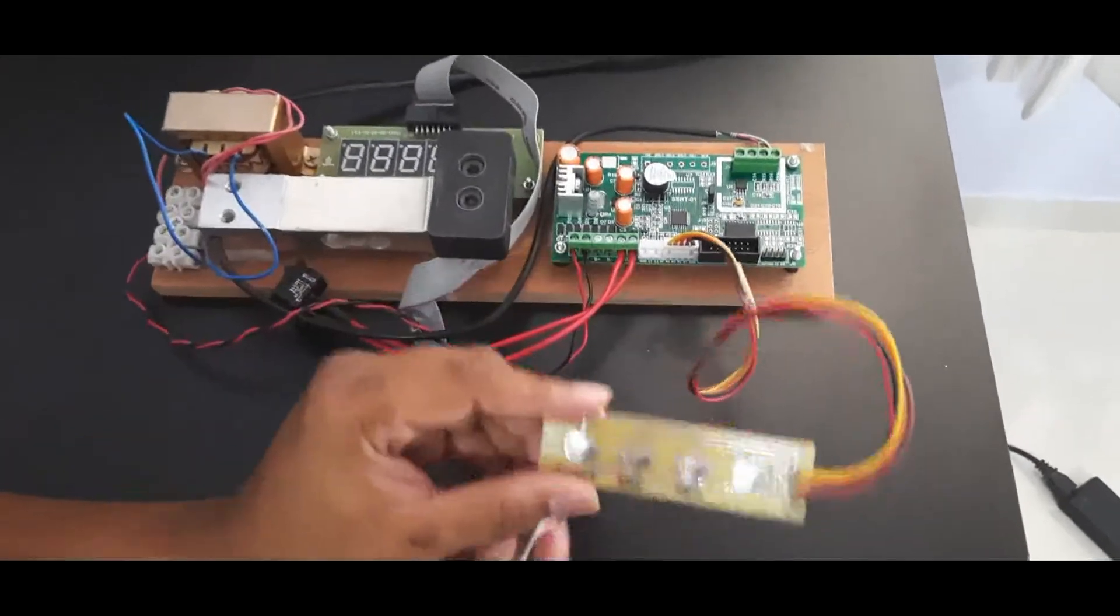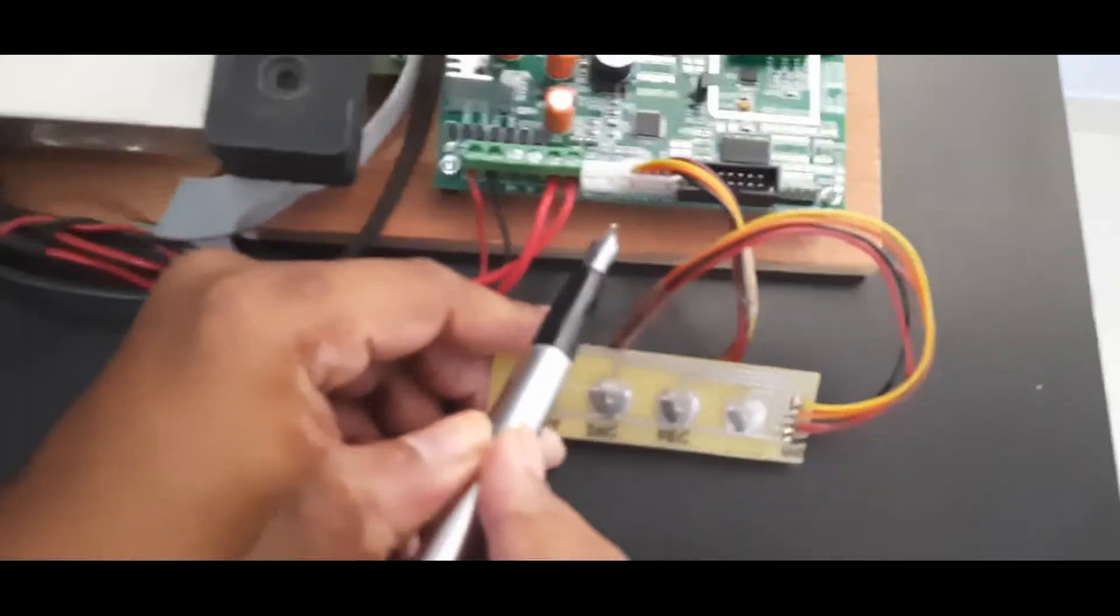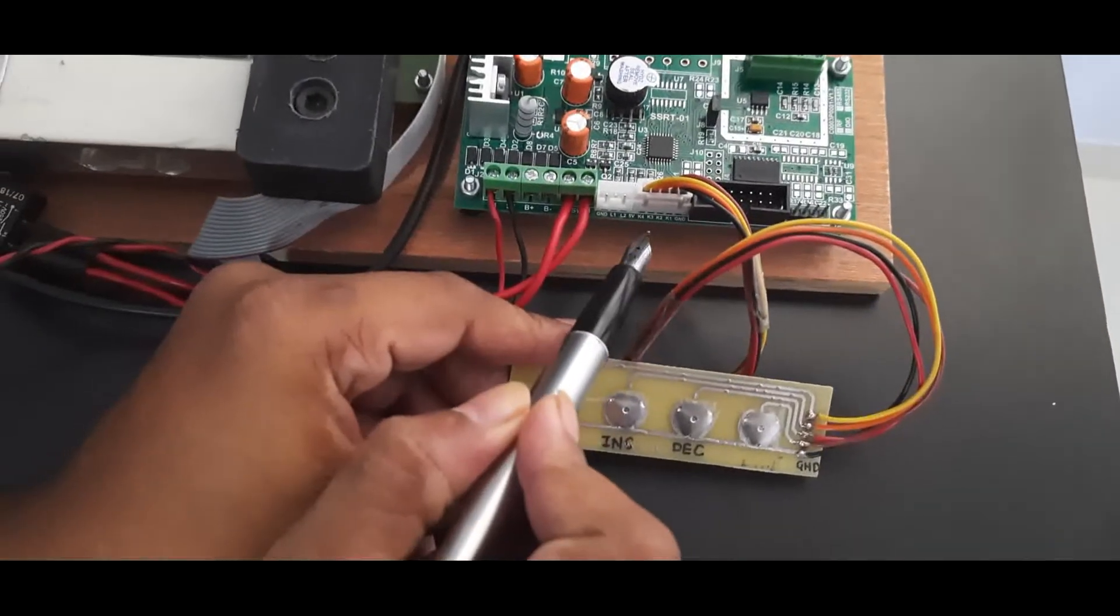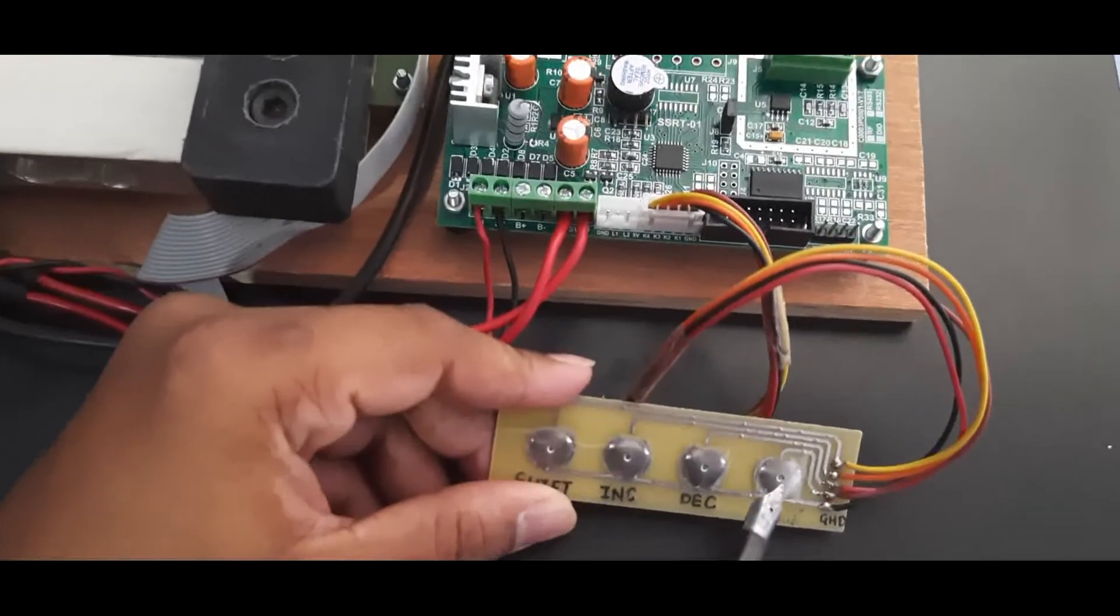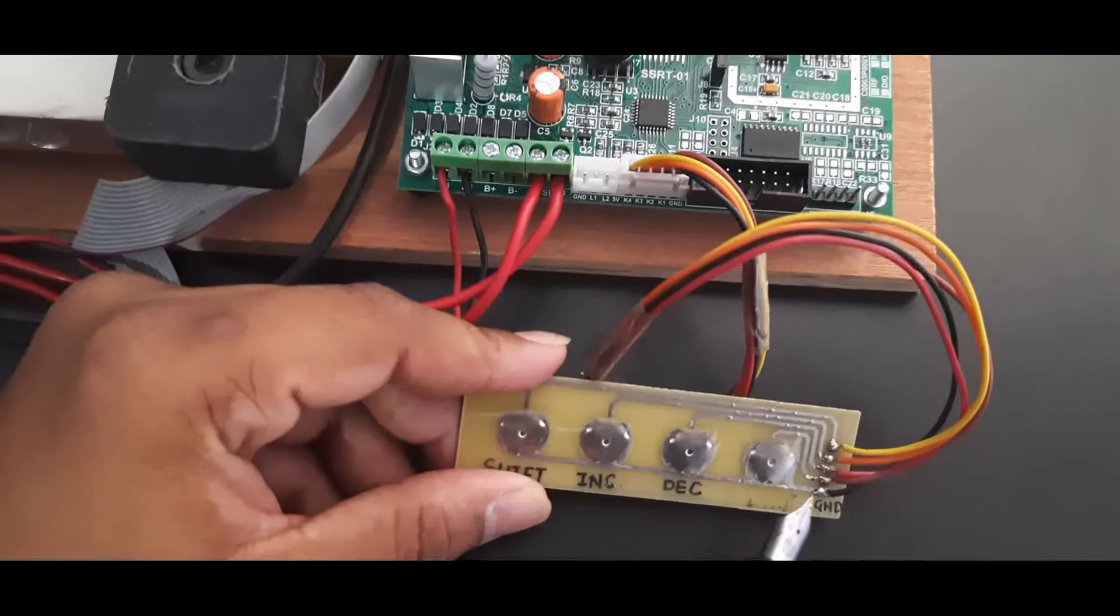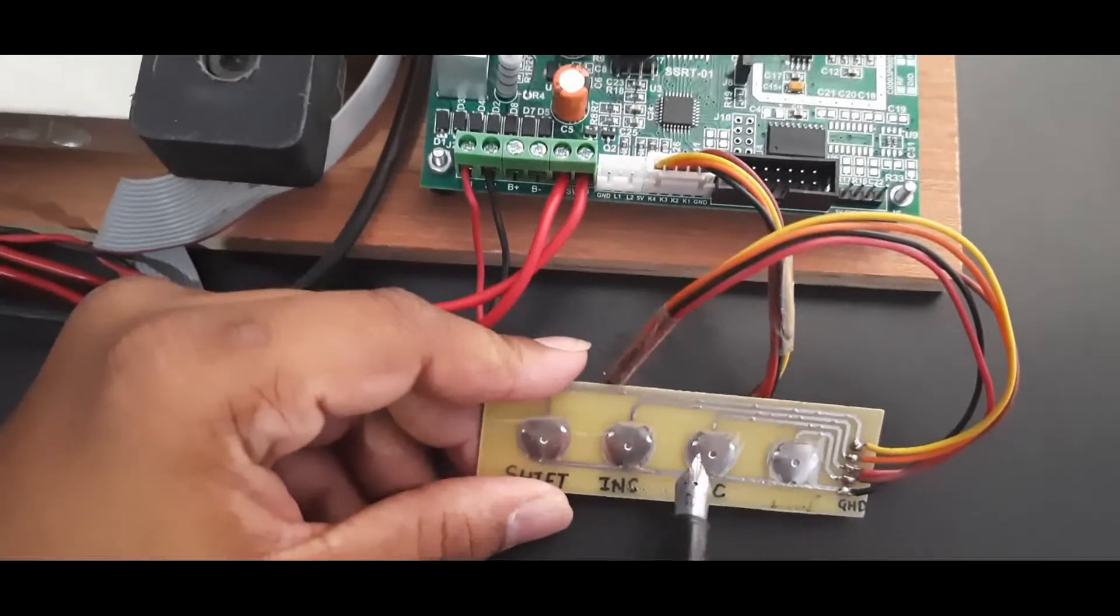Shift key connects to K4, increment to K3, decrement to K2, enter key to K1, and ground is for common connection. This connection is most important, otherwise you will get confused while entering the password or any parameters.